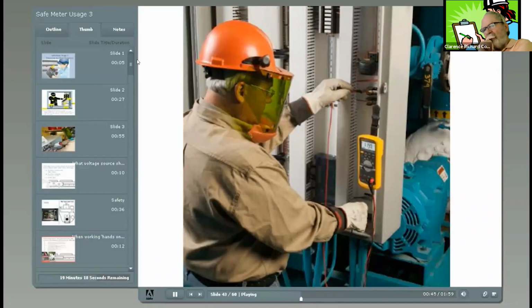On live circuits, use protective gear. Use insulated tools. Wear safety glasses or a face shield. Wear insulated gloves. Remove watches or other jewelry. Stand on an insulated mat. Wear flame-resistant clothing, not ordinary work clothes. When making measurements on live circuits, hook on the ground clip first, then make contact with the hot lead. Remove the hot lead first, the ground lead last. Hang or rest the meter if possible. Try to avoid holding it in your hands to minimize personal exposure to the effects of transients.